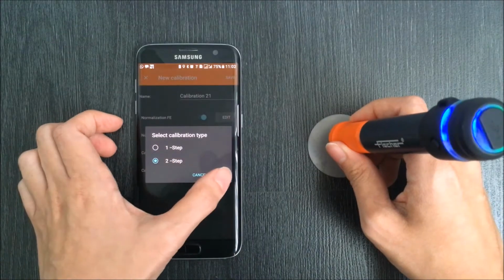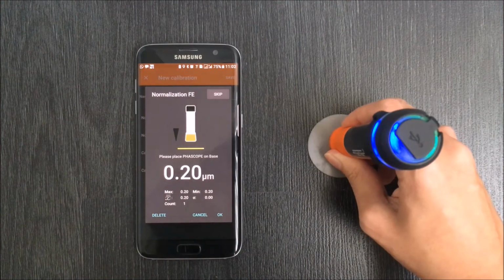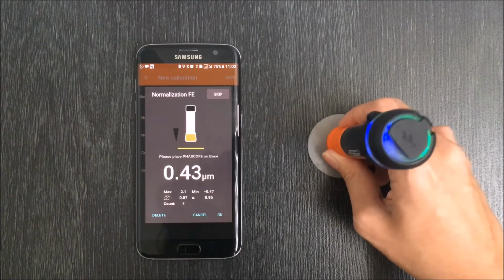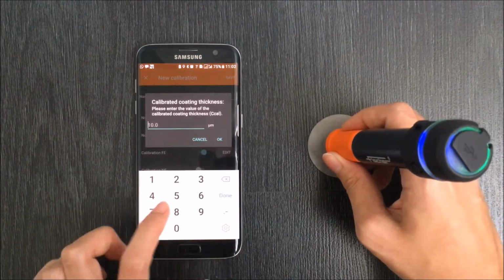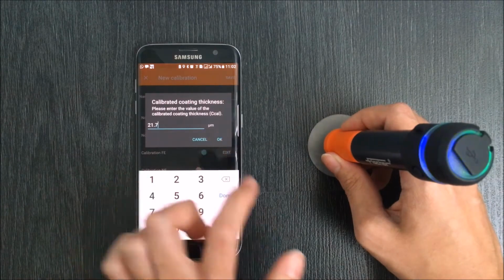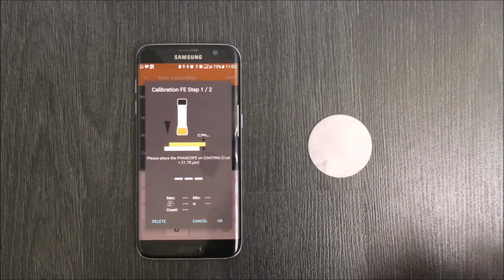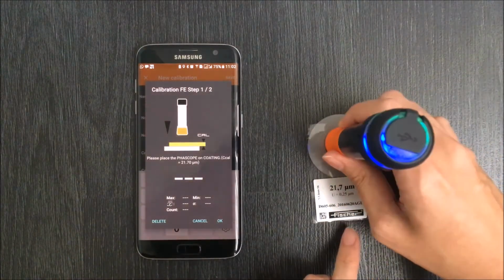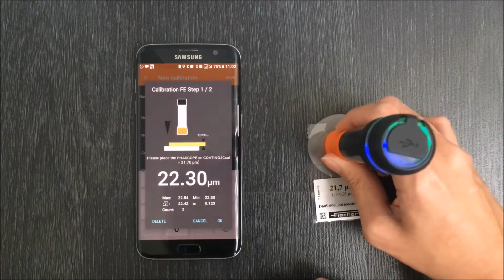When using the setting, the measurement system is adapted to the specimen's characteristics. At least one calibration foil is used, but for the best accuracy, 2 calibration foils, one above target value and one below, should be used for calibration.